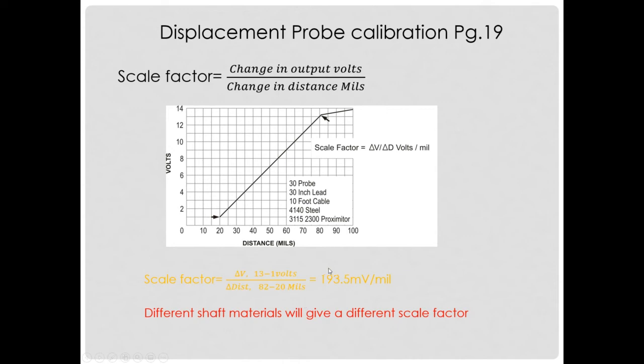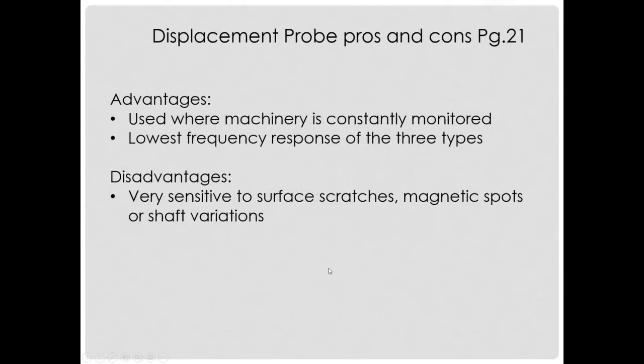Different shaft materials will have a different scale factor — that's why they must be conductive. Advantages of displacement probes: they are typically used where machinery is constantly monitored, and they have the lowest frequency response of the three types. Disadvantages: they are very sensitive to surface scratches, magnetic spots, or shaft variations.